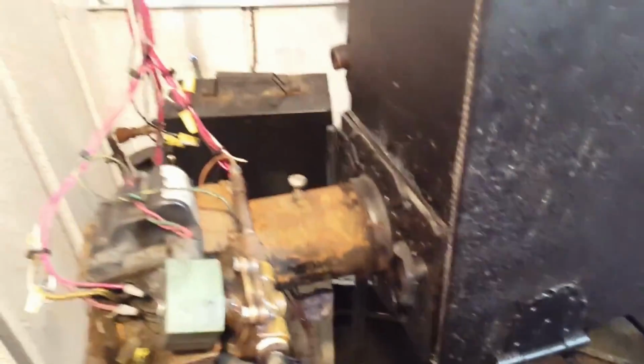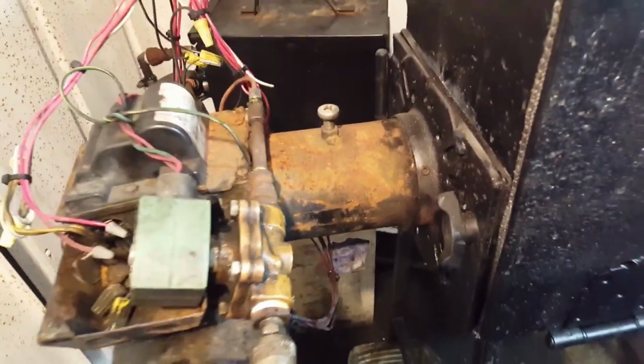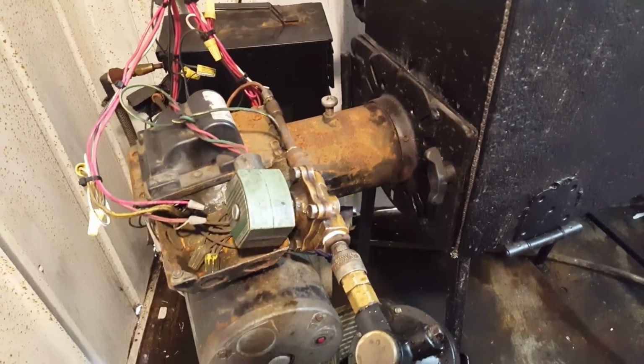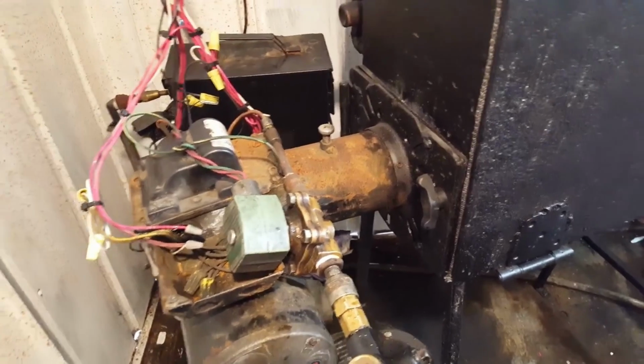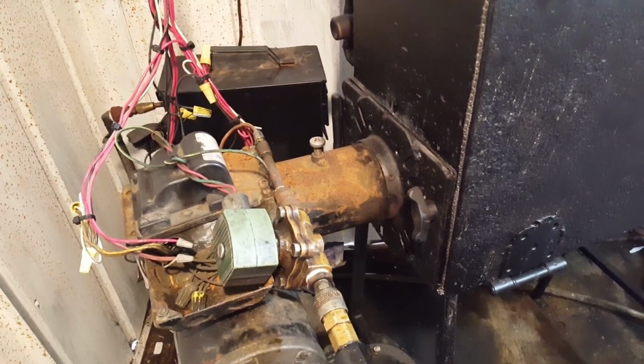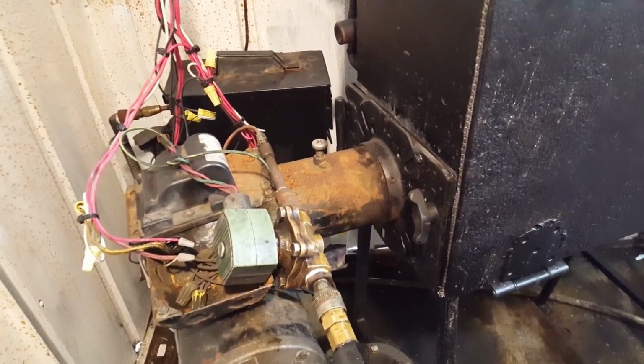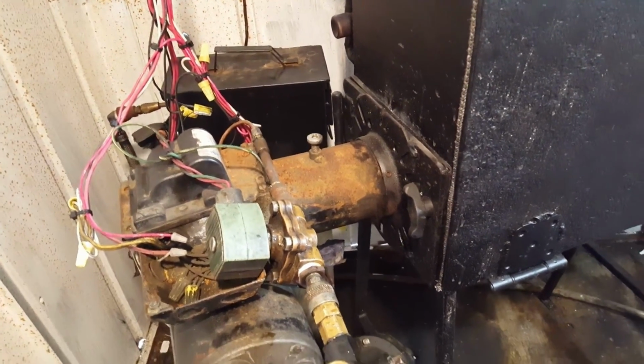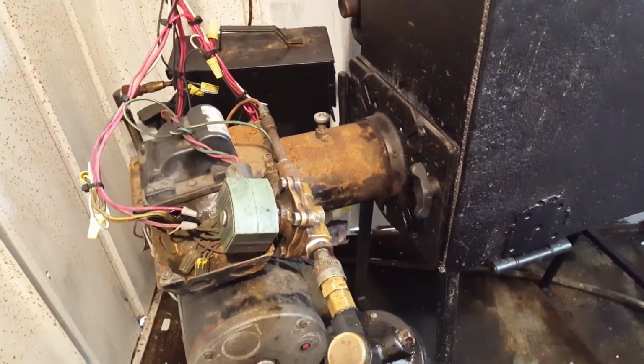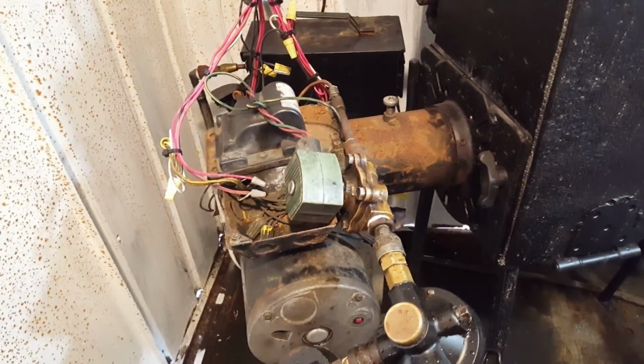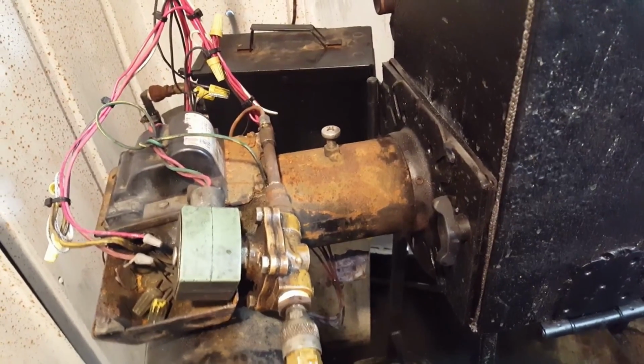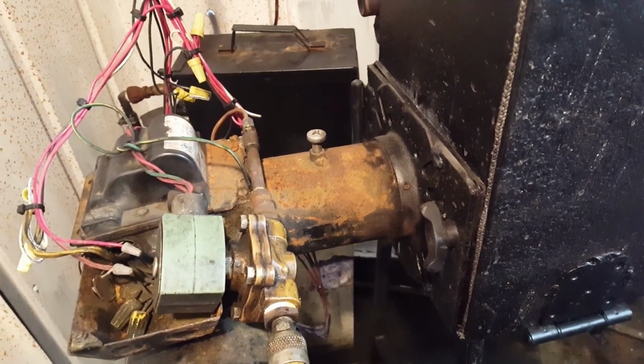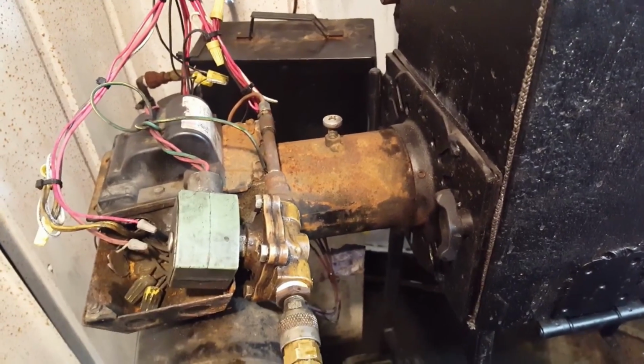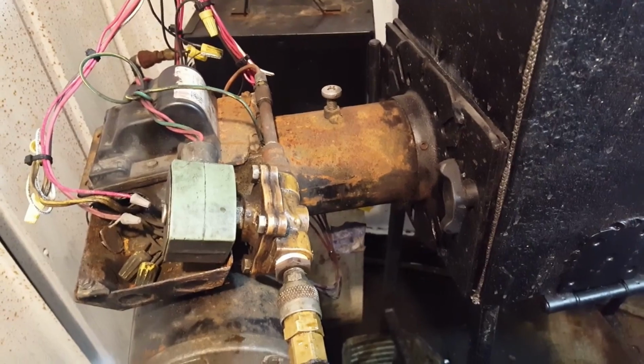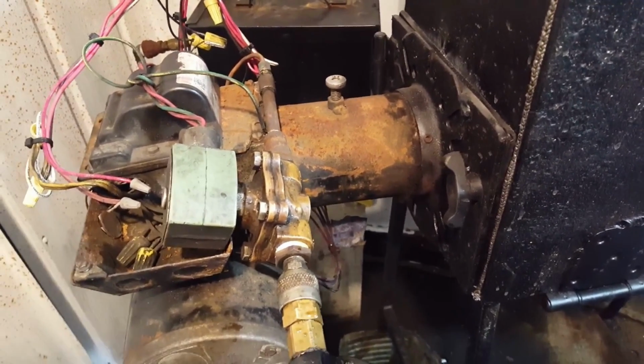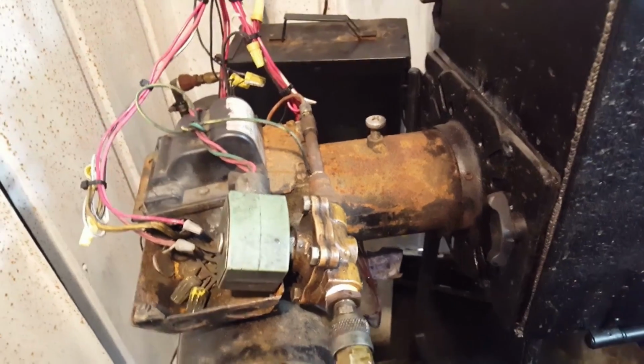Inside that burner tube and inside the end of this burner also, soot builds up and a little bit of oil will drip out of that nozzle all the time. That's just the way it is. And that will get in the end of the burner and the burner tube, and that'll sit there and burn for a little while, causing that flame sensor to see the flame and give an input. So I give it, I think it's 2 minutes for that little flame to burn out. Then it starts checking that flame sensor. If it gets a signal from the flame sensor when there's no call for heat and the burner is supposed to be off, then it'll shut everything down.